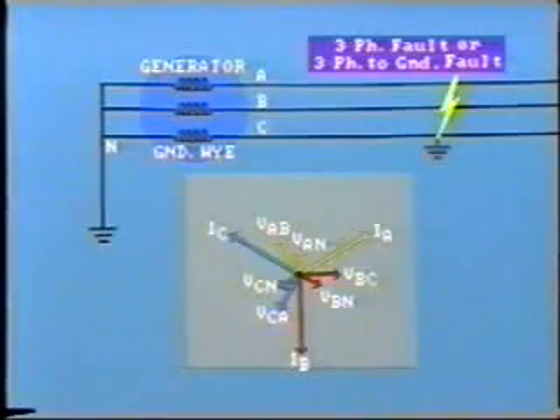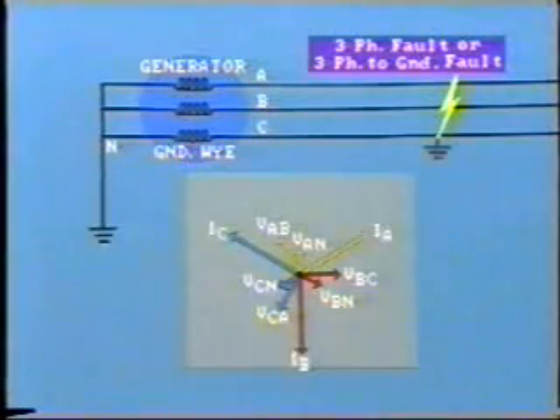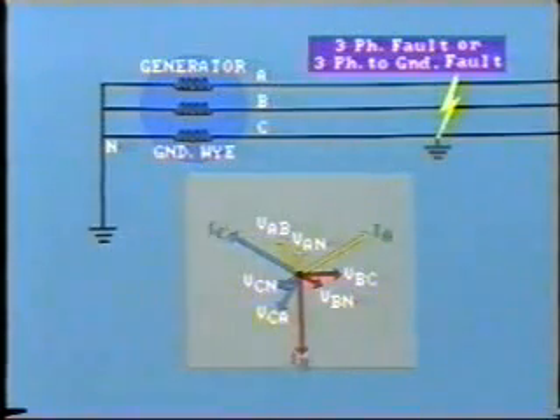At this point, let's quickly summarize the types of faults that we have discussed and their main effects. First, let's look at the three-phase fault and three-phase to ground. At the fault location, the voltage will fall close to zero, and very heavy fault current will flow in all three phases. As in all cases, the magnitude of current is limited by the total impedance of the circuit, plus the impedance of the fault.